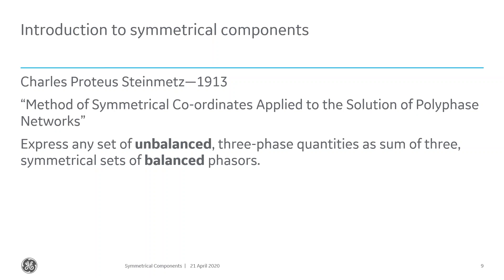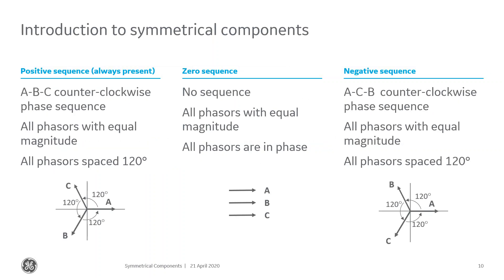When Fortescue developed these mathematical techniques, it let us analyze those systems, calculate fault quantities, and unlock a whole new way to do protection for transmission, generation, and distribution systems. His technique says we can take an unbalanced n-phase system and turn it into different systems of balanced conditions. For our three-phase power system, if I have an unbalanced three-phase system, I can turn it into three separate balanced systems. We describe these as the positive sequence, negative sequence, and zero sequence networks.